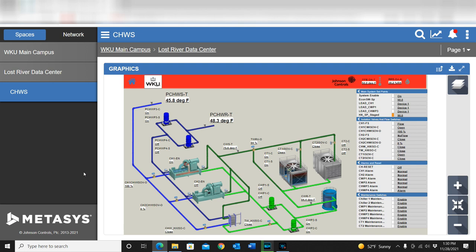Of course, there is enough load on this system that for the most part we would be able to maintain a chiller. However, it is very inefficient to run a chiller year-round, especially when you can take a few steps to conserve energy by using a plate frame system. Now, for those of you who may not be aware, what we are doing in the plate frame system is once outside air falls below a particular set point, which currently in this system we're running at around 50, once outside air temperature falls below that 50 degree mark, it will actually shut down the chiller and use the cool outside air temperature to cool the water using the heat exchanger.